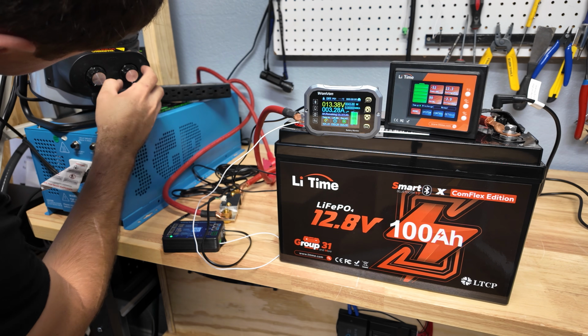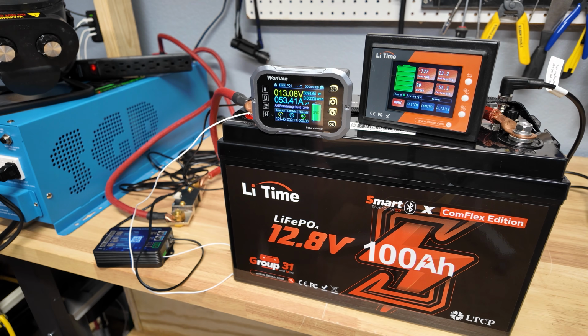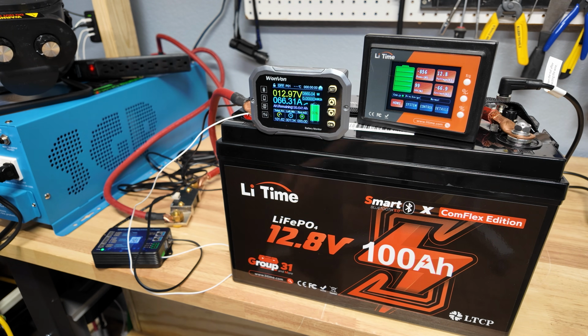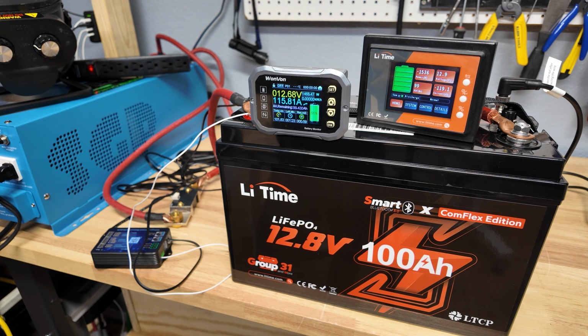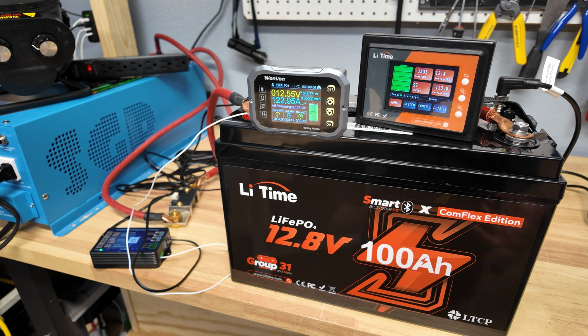Space heater is going to be on low to start. That's 50 amps right there. I'm going to crank the space heater up to high. We're just over 100 amps. I'm going to let it run and see if it shuts off. We're at 120 amps, see how long it'll run it for. That's 1500 watts of load. Doesn't seem to mind running above 120 amps.